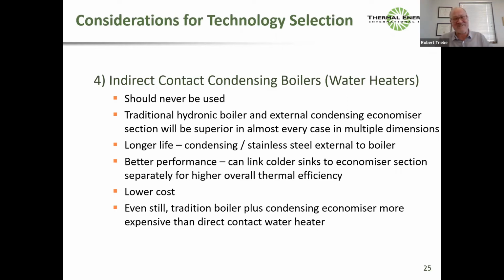There's plastic heat exchangers out there that are good for high temperature, but direct contact becomes a wet scrubber and you end up with a huge water treatment concern. So, just to do heat recovery, the direct contact wet scrubber is not ideal. And you have to go to exotic metals, Hastelloy, or even fiberglass. And the indirect unit certainly can't be used on bunker. I'm sorry. On bunker, you would have to go with the more severe, and I would probably recommend the Teflon coated or even plastic heat exchangers that are available, designed specifically for high sulfur streams.